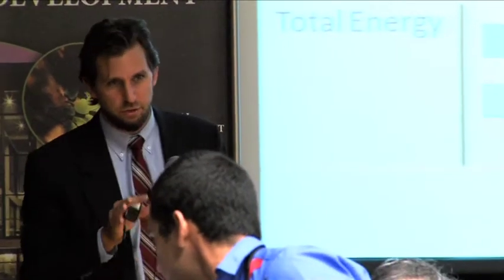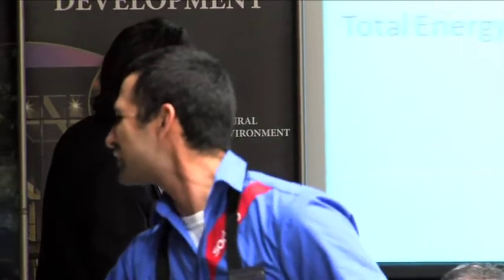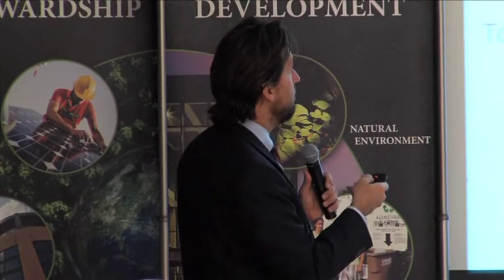Okay. So that's sort of the chemistry of it, but what you really need to think about is, in the practical implementation, what that means is I can reach the same level of humidity at 70 degrees and never go below that, as this equipment needed to go to 55 degrees to reach. And that has multiple benefits.